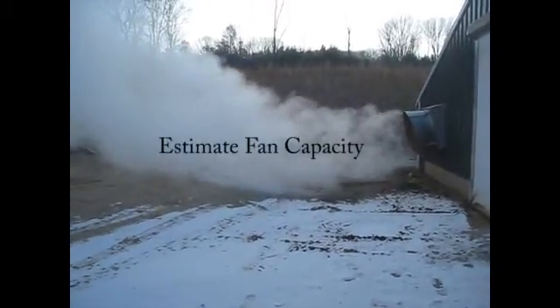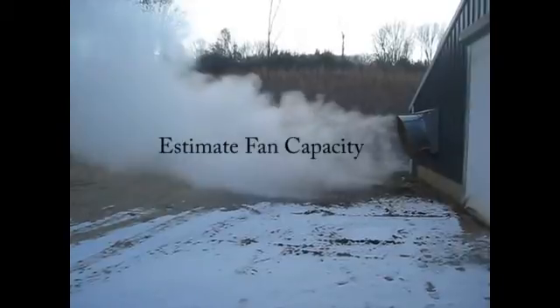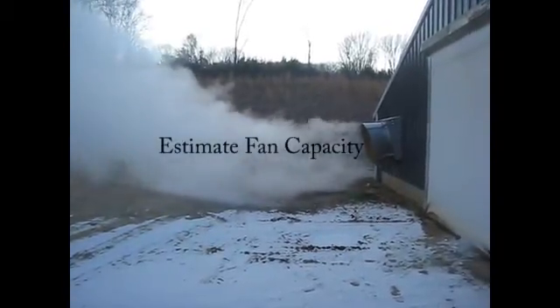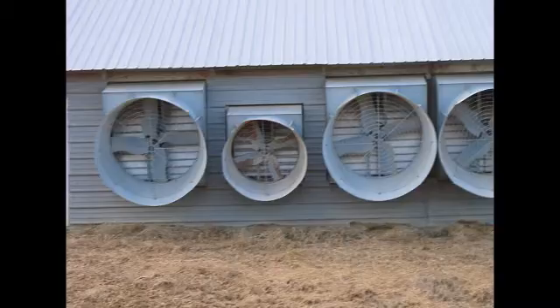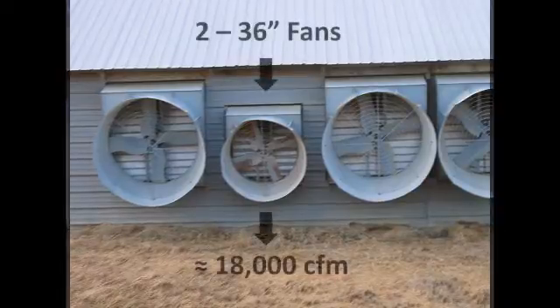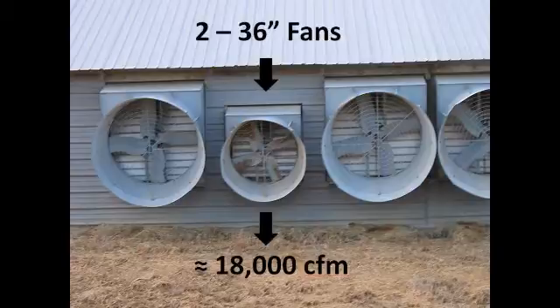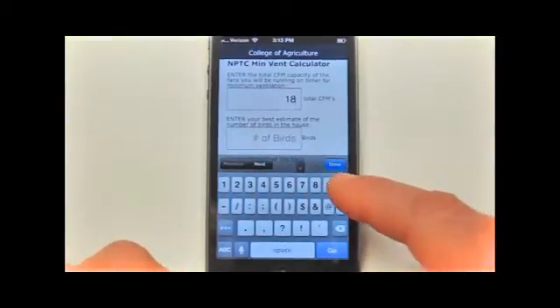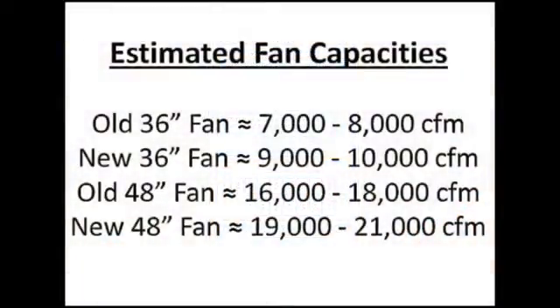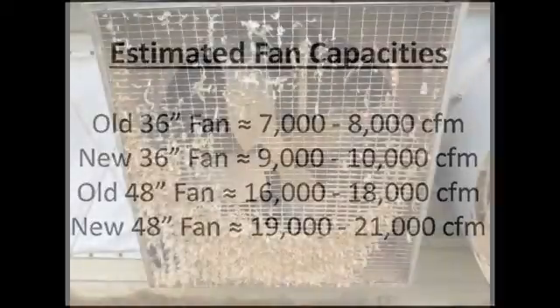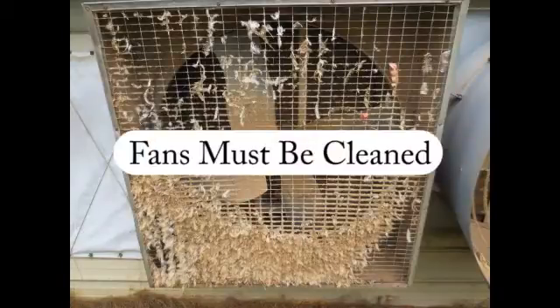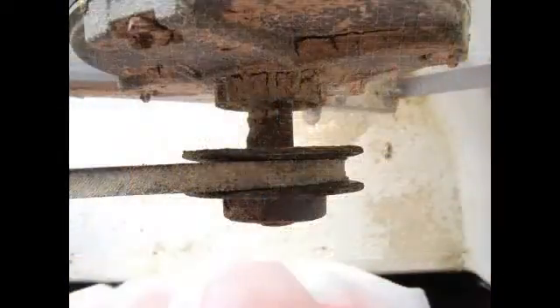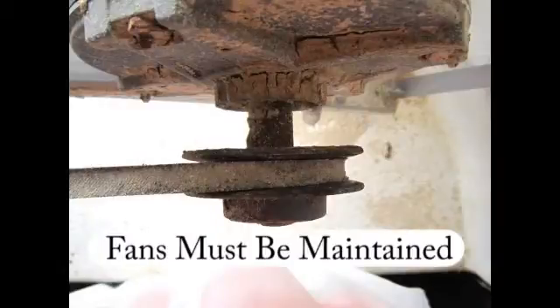The first step to calculate fan runtime is to estimate the total cubic feet per minute of fan capacity that you will be using for minimum ventilation. For this example, we are using two 36-inch fans for a total fan capacity of 18,000 cubic feet per minute. Type 18,000 into the mobile calculator where the blank reads total CFMs. Estimated fan capacity varies based on the size, age, and condition of each fan — routine fan maintenance and how it affects fan output cannot be overstated.